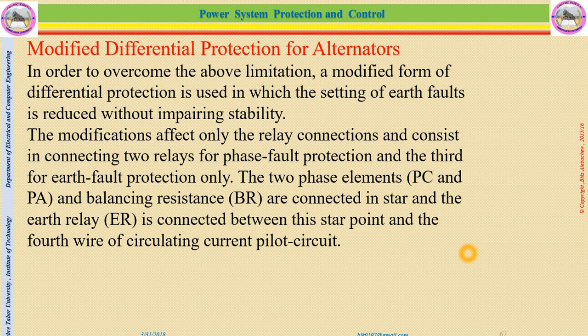Modified differential protection for alternators. In order to overcome the above limitation, a modified form of differential protection is used, in which the setting of earth faults is reduced without impairing stability. The modification affects only the relay connections and consists in connecting two relays for phase fault protection, and the third one is for earth fault protection only.